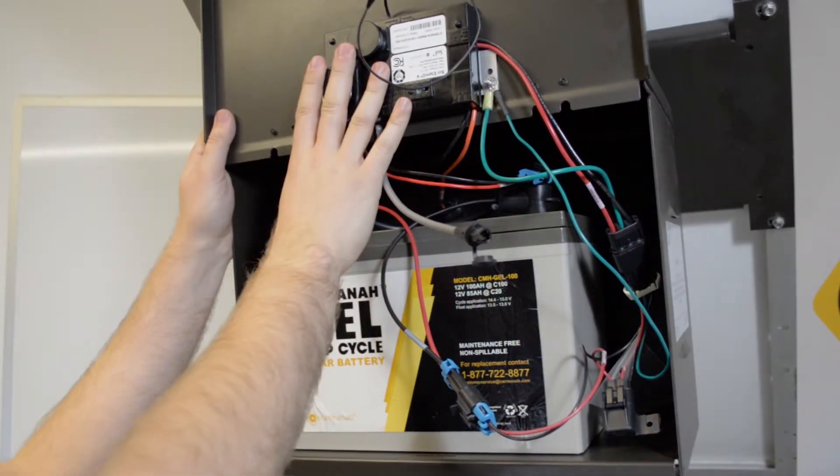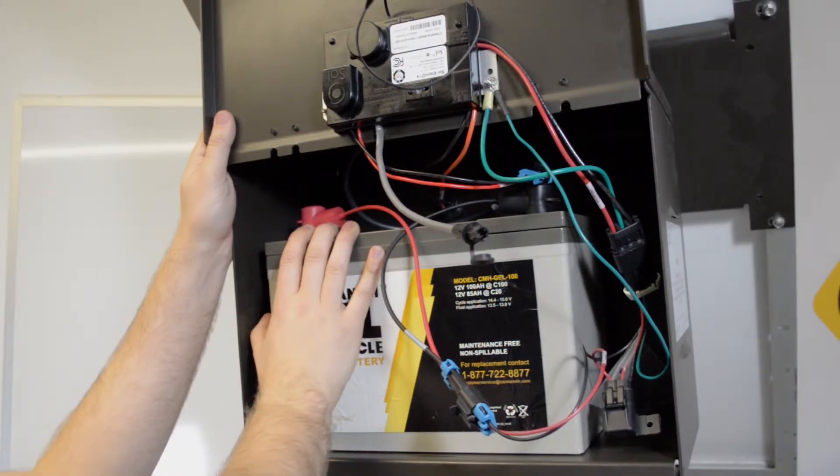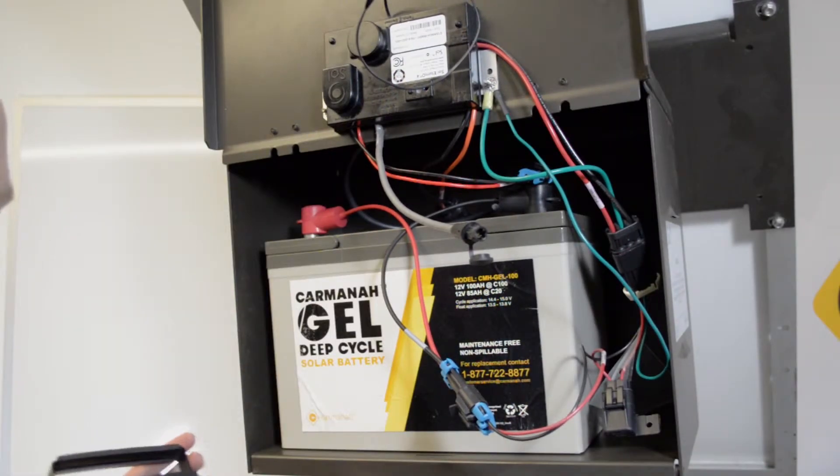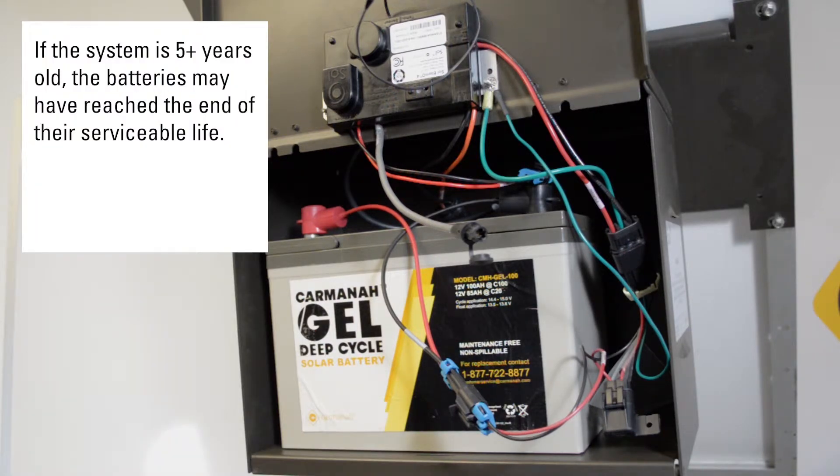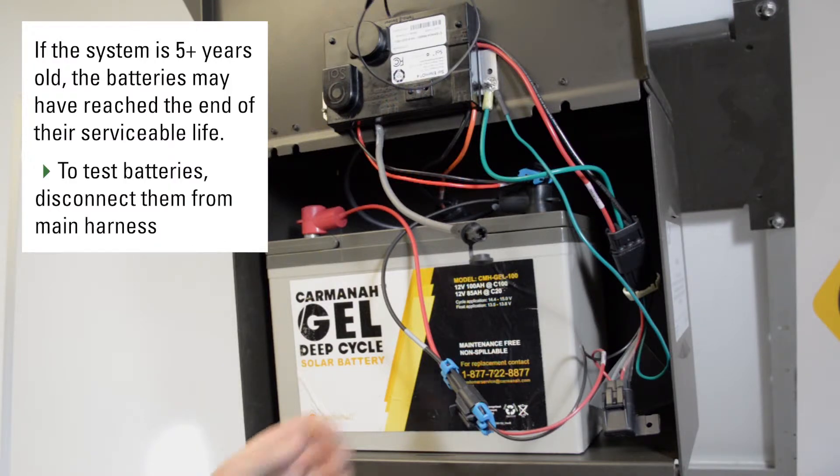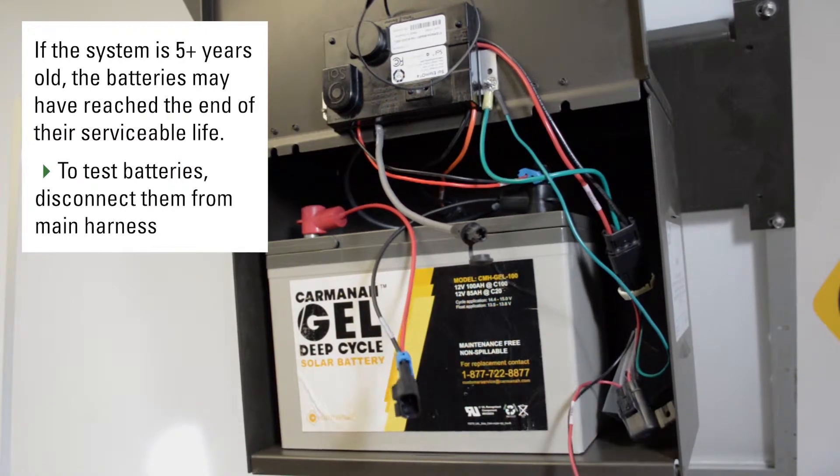If there were any issues with the EMS and there have been prolonged charging issues, the batteries themselves may be damaged and need to be replaced. The best way to test the batteries is using a load tester. If the system is over five years old, the batteries may have reached their serviceable life. To properly test the batteries, disconnect them individually from the main harness.